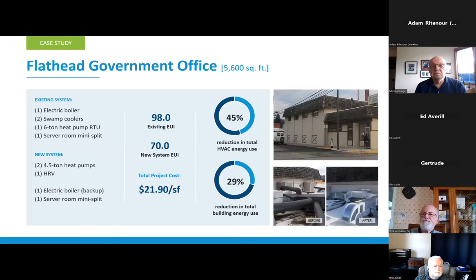So I've got a couple of other projects that I wanted to highlight, and these are Montana projects. So these are cold climate projects. The first one is Flathead Government Office. You'll see that they started off with an electric boiler, swamp coolers, a 6-ton heat pump RTU, and a server room mini split. They kept the electric boiler as a backup and also the server room mini split because that was kind of standalone. But they did replace their swamp coolers and that heat pump RTU with 2 4.5-ton heat pumps and an HRV. So still significant savings, 45% reduction in total HVAC energy use, but only a 29% reduction in total building energy use.